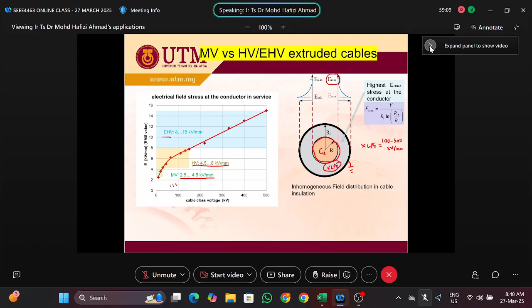Okay, so basically XLPE has like 100 to 300 kV per millimeter. Okay, and now you might see that the electric fields at the surface of the conductor, if the voltage that we apply is somewhere around 11 kV to 23 kV, will vary within this range, 2.5 or so. So of course you might see that this field strength value is less than the electric strength of the XLPE. Okay, this is acceptable. And of course, this cable can be installed in the field and can be energized. But, okay, what happens if we have a void?